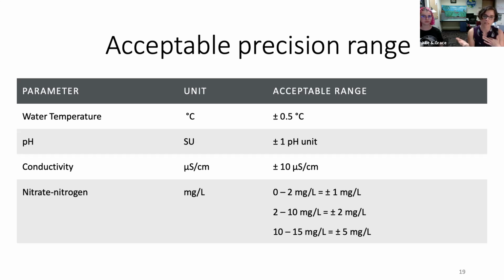Your acceptable precision range is based off of the equipment sensitivity and what we would expect to see at certain values. So for water temperature, it's half a Celsius unit of measurement. For pH, we're looking for ±1. Conductivity, we're looking at ±10 microsiemens per centimeter. And then nitrate nitrogen gets a little tricky because our kit has different ranges for nitrate nitrogen, so we have different acceptable precision ranges based on the ranges of the kit.